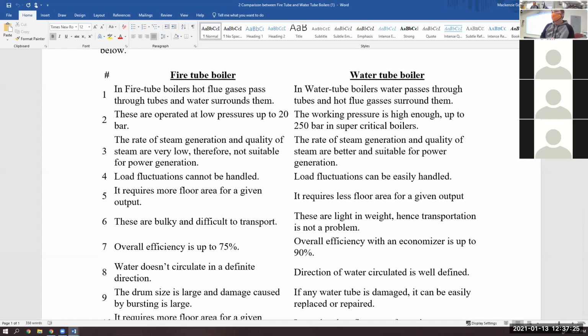Yeah, there's less water, so instead of the heat going into a big amount of water, it gets dissipated differently. We're taking the water and making it so flue gas can get around the entire circumference of a small piece of that water. We're essentially breaking the water up into smaller parts and heating those smaller parts faster, getting more steam generation, rather than having a big pool of water and trying to make sure the flue gas passes evenly through all of it to heat it equally and quickly. So it does have to do with heat transfer, but I think your statement is the most correct - you're breaking the water into smaller pieces to heat rather than a big tub of water that heat passes through.